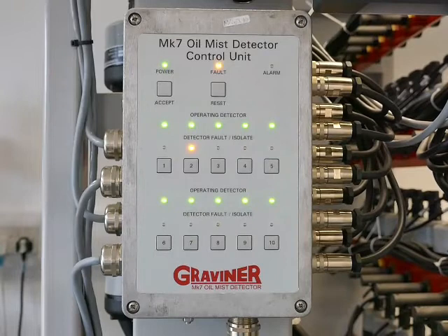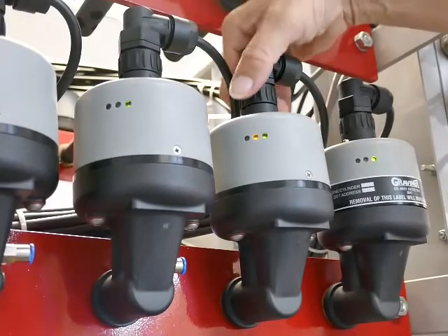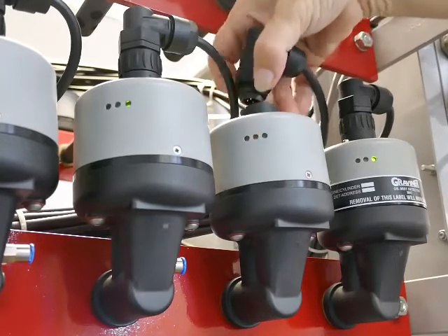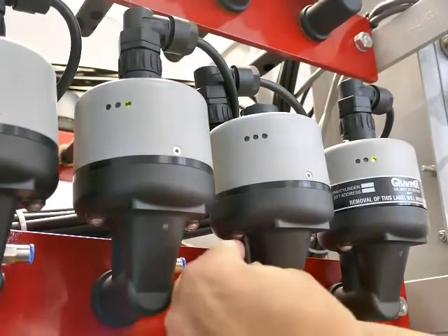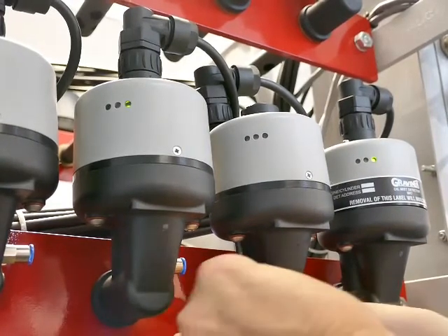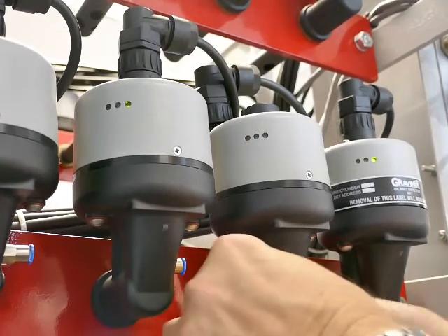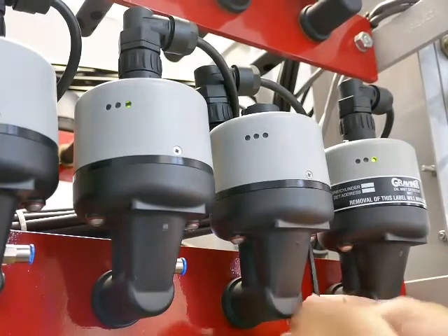On the engine's control unit, the common fault LED will be flashing, indicating the fault is on that engine, and the detector fault LED will be on constant, indicating the detector is isolated. The detector will also have its yellow fault LED on. Firstly, disconnect the detector cable from the detector. Although the detector is isolated, it can still cause a backup alarm when the detector head is removed from the base. Remove the head by undoing the 2 Allen head screws in the base.